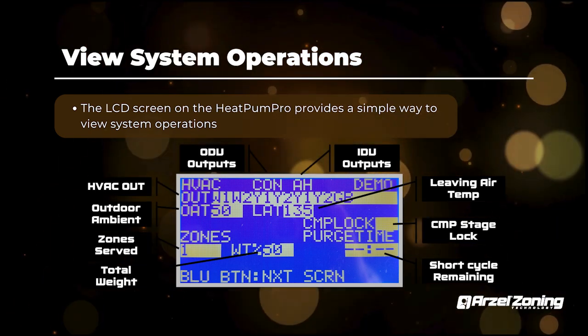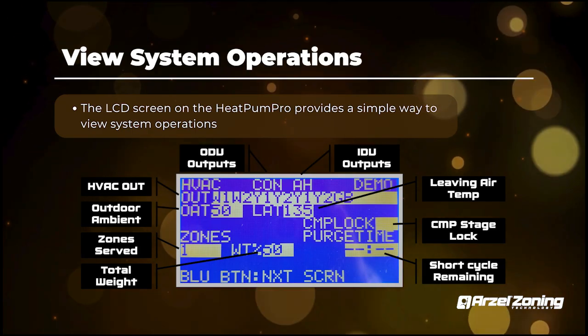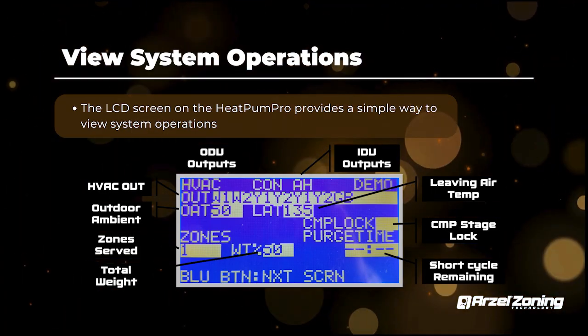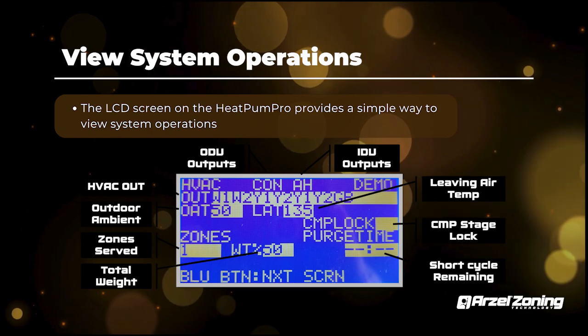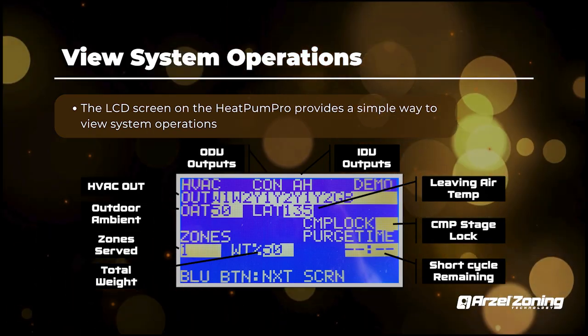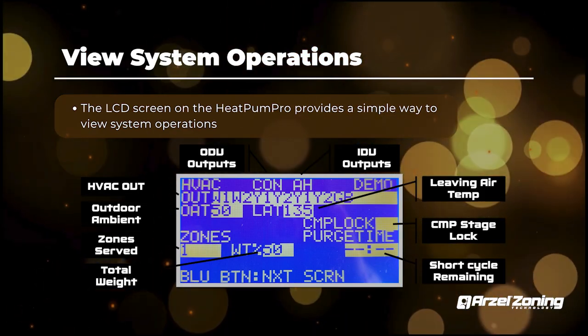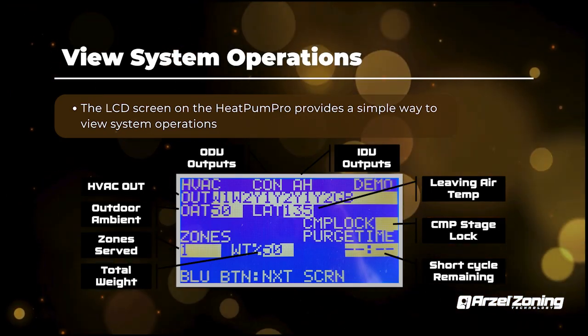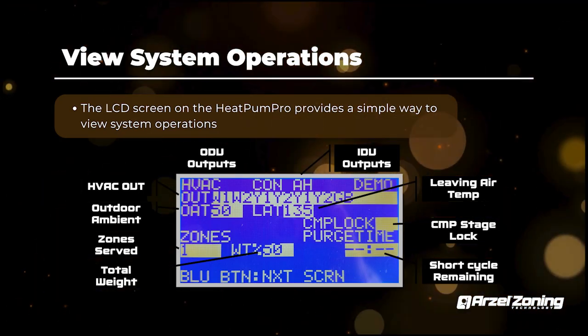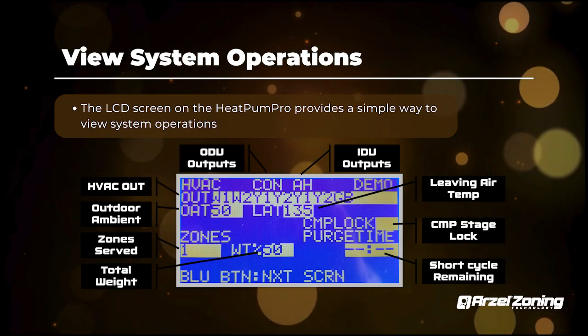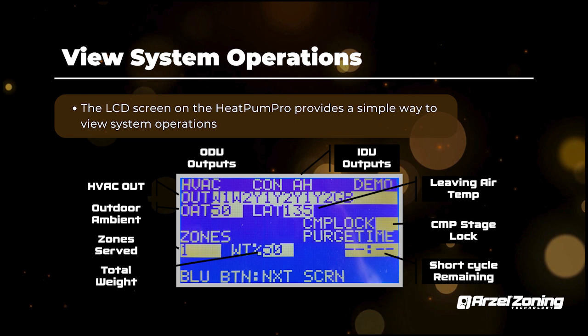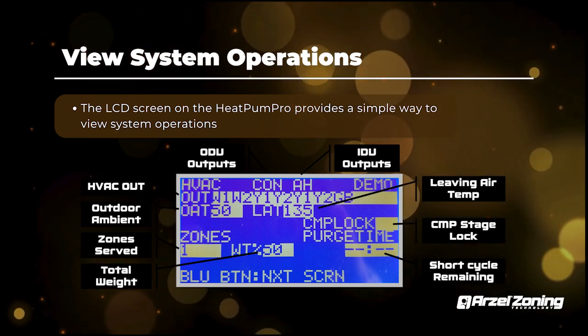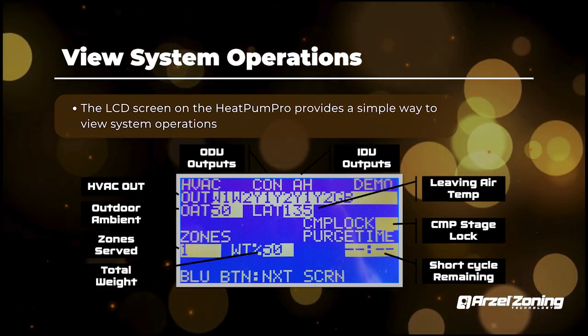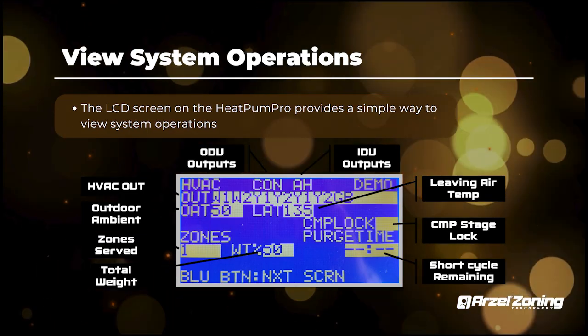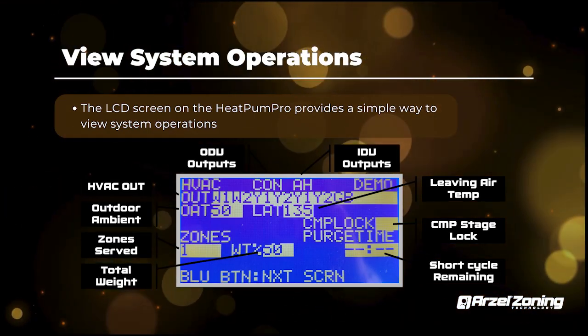Right underneath that is your purge time. You'll never see anything on that line unless all the calls are just satisfied on the panel, and then you'll see a countdown. This is settable in your setup wizard for the HeatPumPro, so you actually set your purge time. When you do that, it's 5 seconds per damper. So count your dampers, multiply by 5. That's where you'll set that purge time. And that's essentially how long we run our purge at the end of the call. So once your call is satisfied, it makes sure all the dampers are open at the start of the next cycle. So that's all that is. You'll see it anytime all the calls are satisfied on there. Then kind of on the left in the middle there, you see zones. There'll be a number 1 through 4 on there.